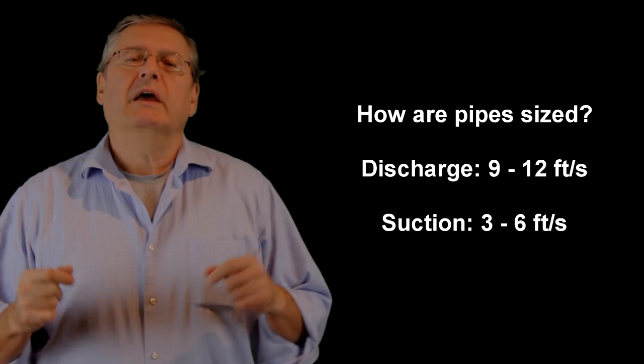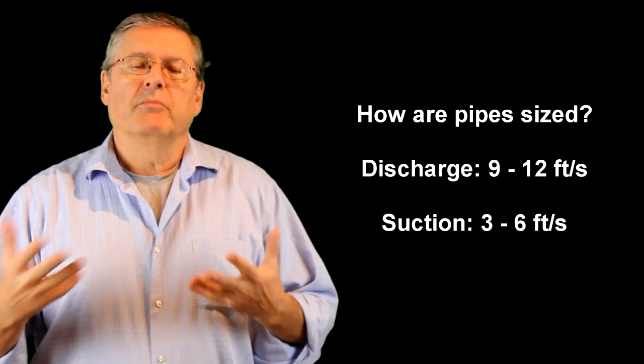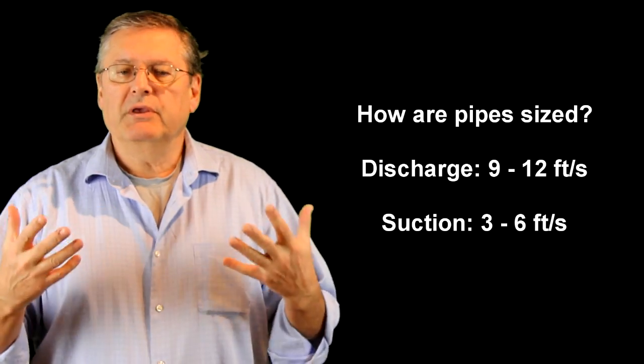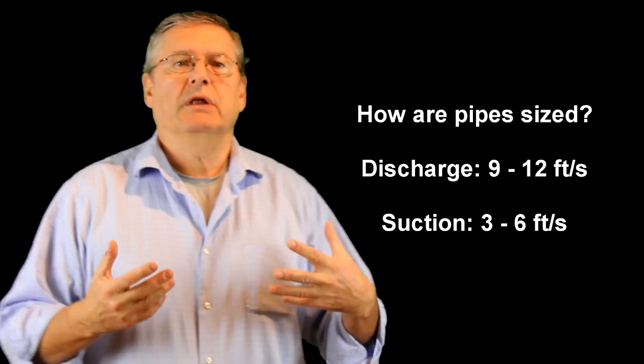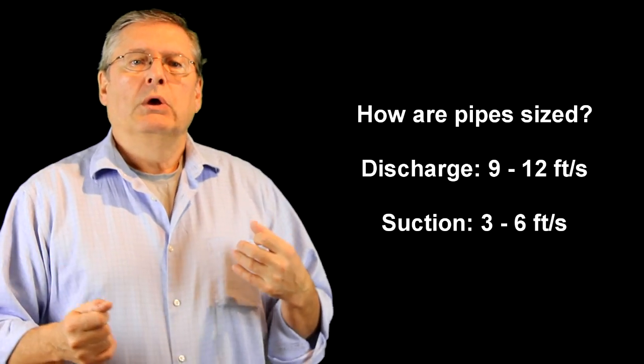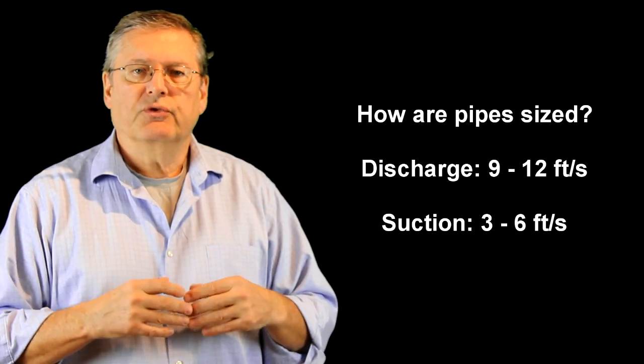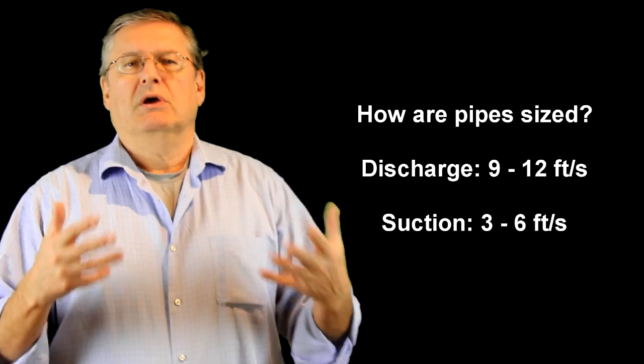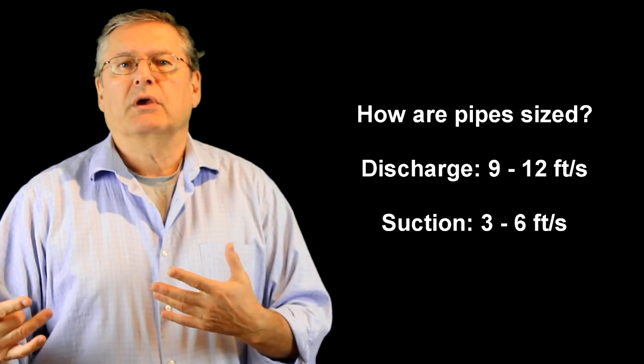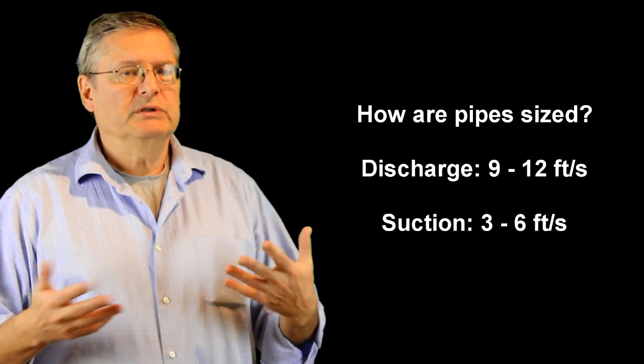How are pipes sized in systems? Well there's some guidelines. Generally speaking, on the discharge side we want the liquid to move rather a bit more quickly. We don't want the pipe size to be unnecessarily large. A good guideline is somewhere between nine feet per second and twelve feet per second. It could be less or more for various reasons.